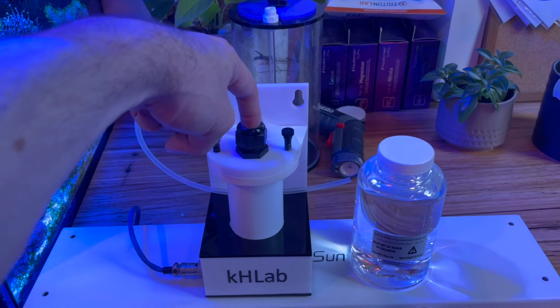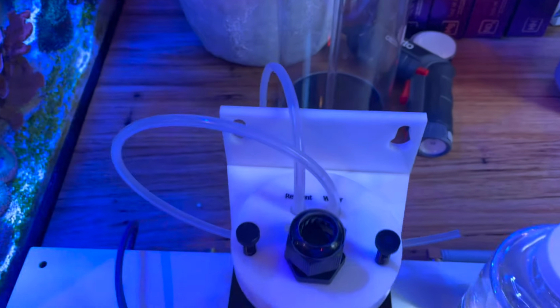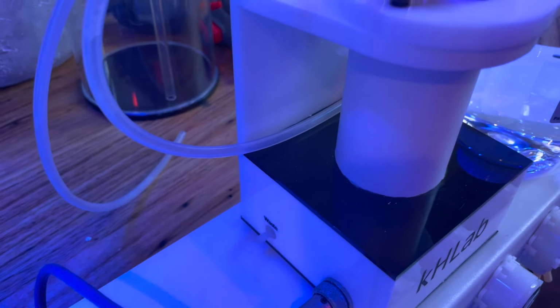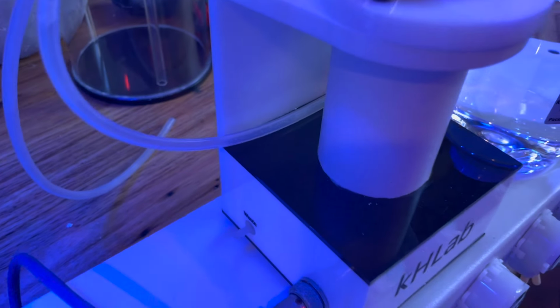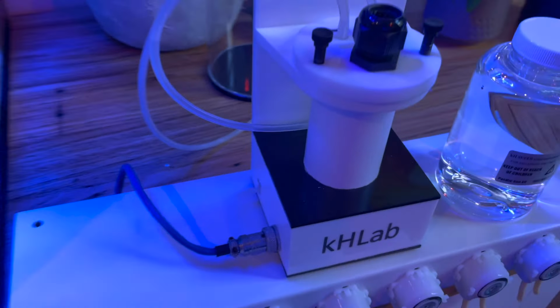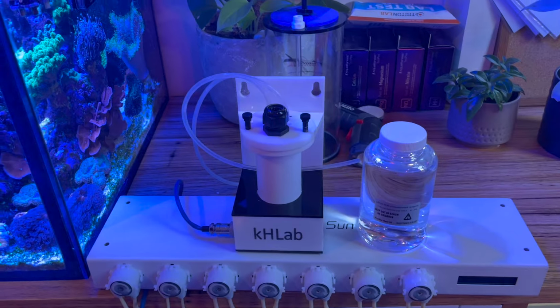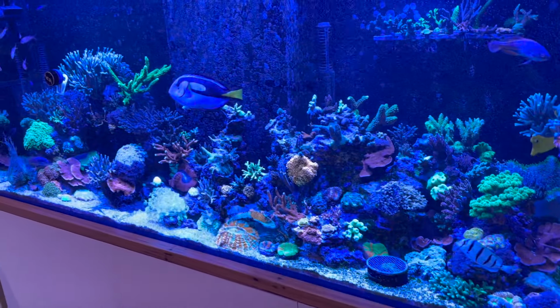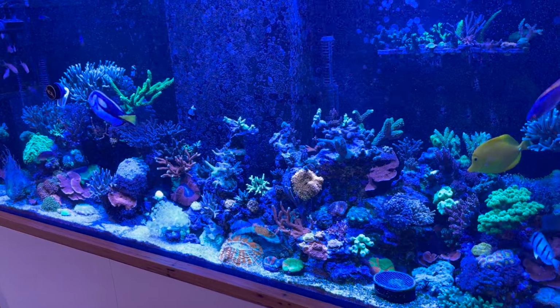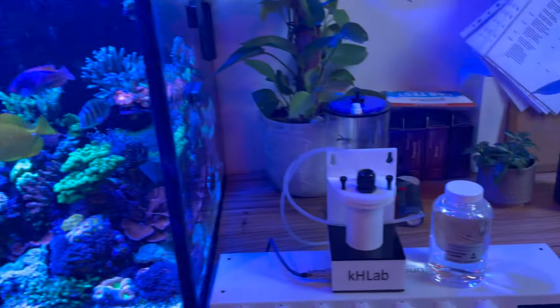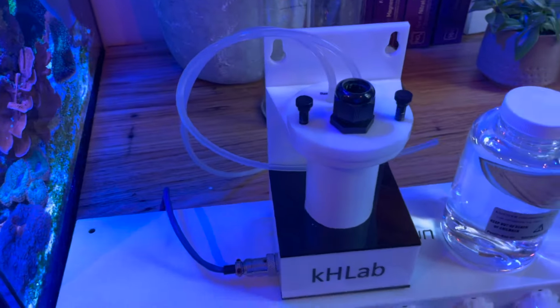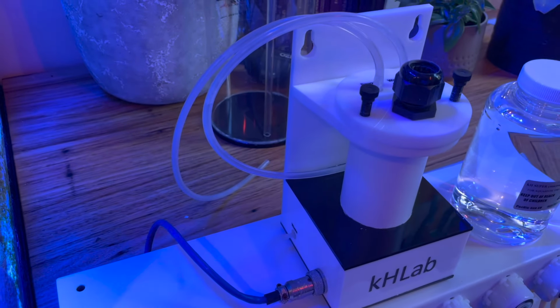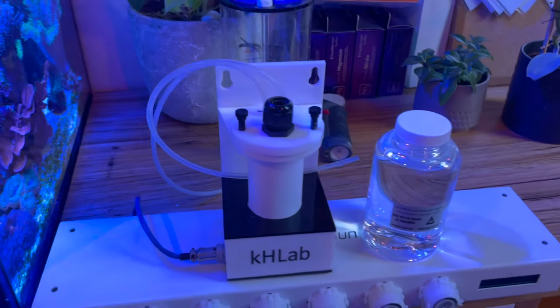A pH probe goes in here, and then there's two inputs on the top, one for reagent and one for salt water. And then there's an output on the side for the wastewater. For me, I've always just fed the wastewater back into the tank. It's perfectly safe to do so. I've been doing that on my tank for 3 years now, and as you can see, there's really no negative side effects that I've ever noticed from doing that. It's perfectly safe. But if you are paranoid about that kind of thing, you could feed the waste line out to a drain or a waste bottle of some description.